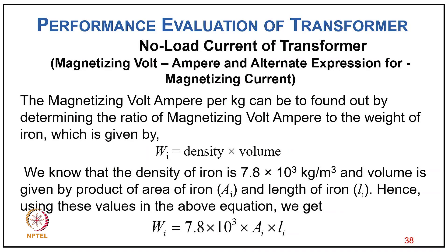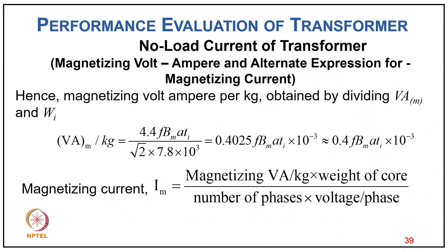The magnetizing volt-ampere per kg is found by dividing VA(m) by the weight of iron Wi = 7.8×10³ × Ai × Li. This gives magnetizing VA per kg = 4.44 × f × Bm × ati / (√2 × 7.8×10³) ≈ 0.4025 × f × Bm × ati × 10⁻³, or approximately 0.4 × f × Bm × ati × 10⁻³. The magnetizing current Im is then: (magnetizing VA per kg × weight of core) / (number of phases × voltage per phase).